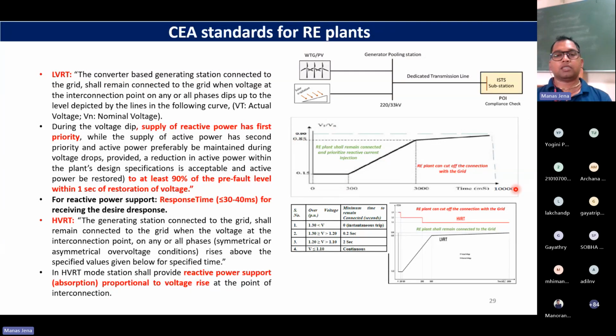This is the time axis, and this is the voltage, Vt upon Vn, terminal voltage upon nominal voltage. Let us say this is 0.85 per unit and this is 0.15 per unit. If the voltage is in this region for this much time, you should remain connected to the grid, and if it is beyond that, you can disconnect yourself. That is what LVRT is. The name is low voltage ride through.